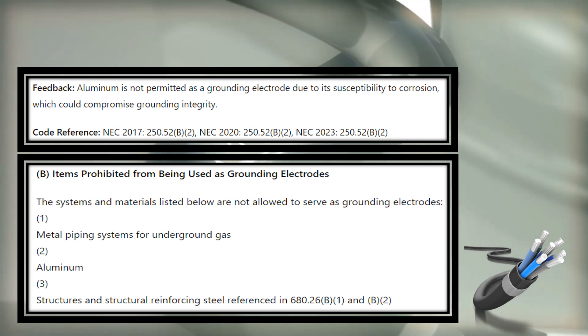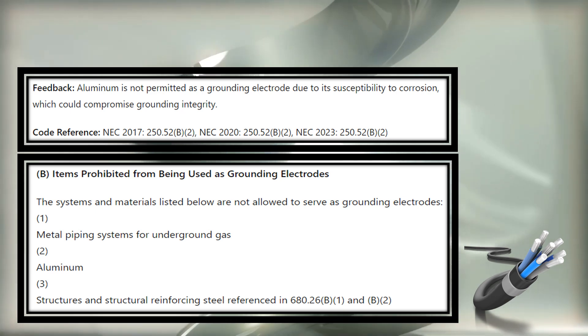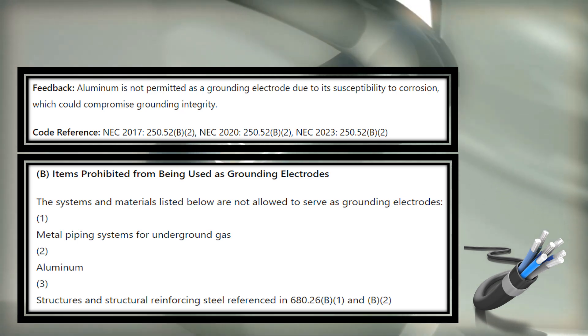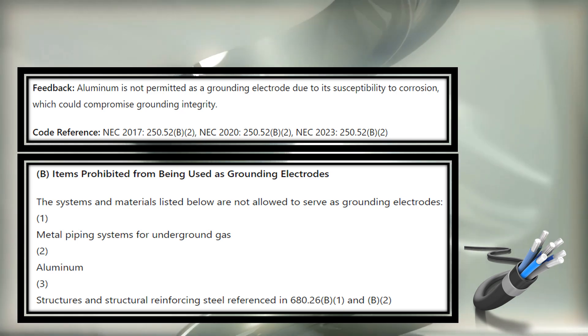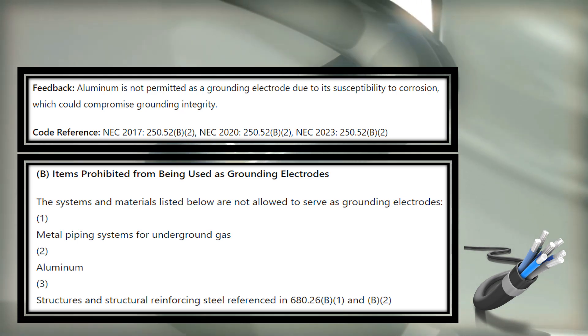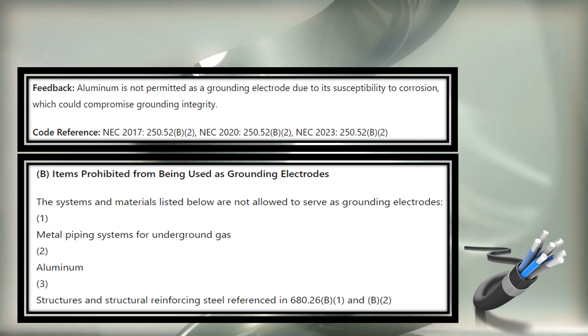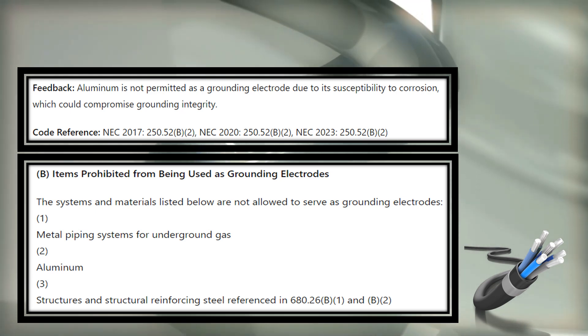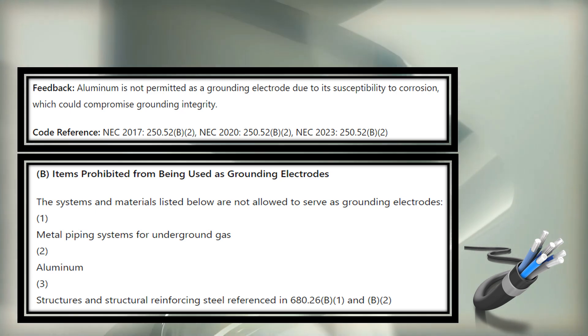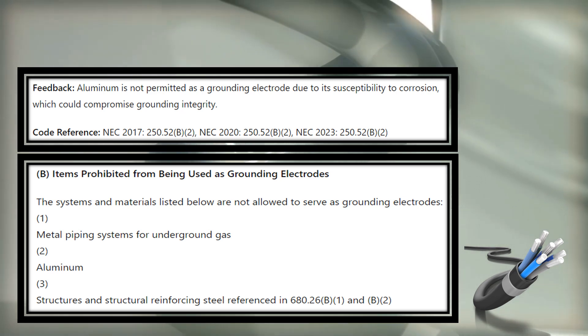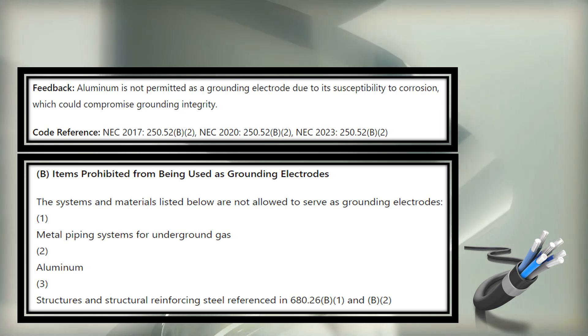And then structures and structural integrity of reinforced steel, and the steel that is referenced in 680.26 — which is our pool equipotential bonding grid — we're not allowed to use any type of the pool structure as part of our grounding electrode system.